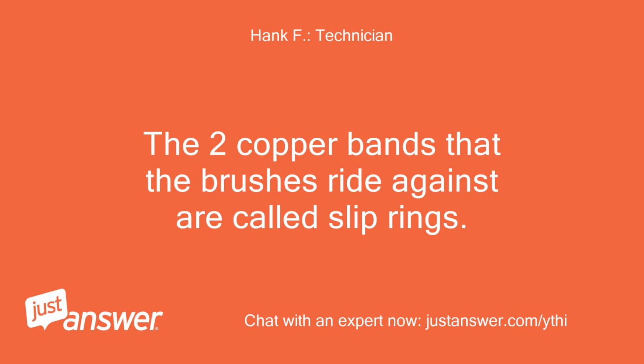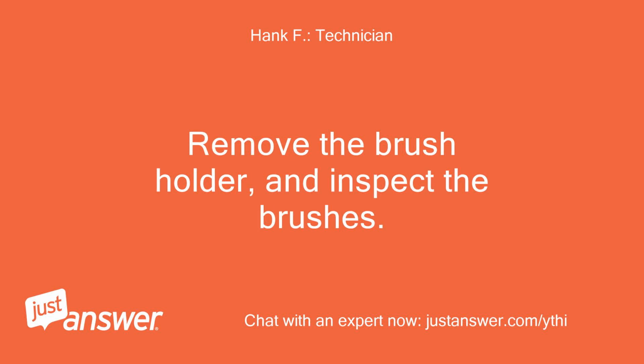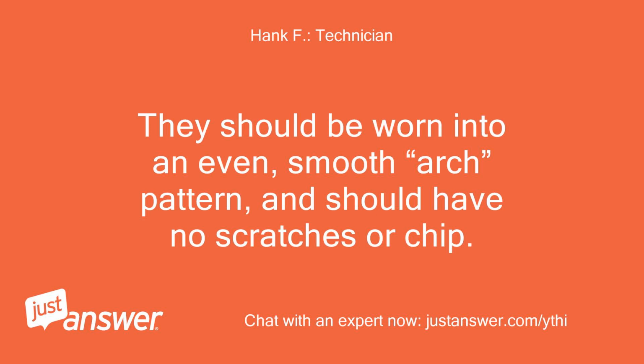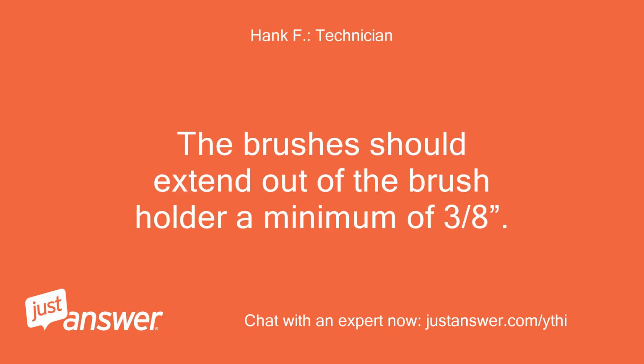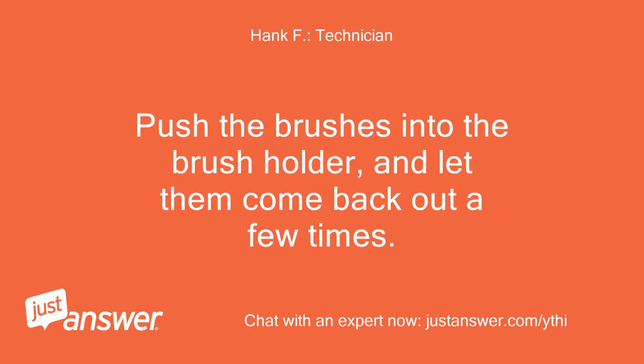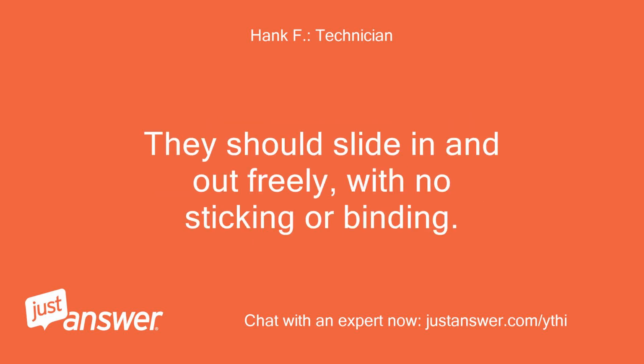The two copper bands that the brushes ride against are called slip rings. Remove the brush holder and inspect the brushes. They should be worn into an even, smooth arch pattern, and should have no scratches or chips. The brushes should extend out of the brush holder a minimum of 3/8 inch. Push the brushes into the brush holder and let them come back out a few times. They should slide in and out freely, with no sticking or binding.